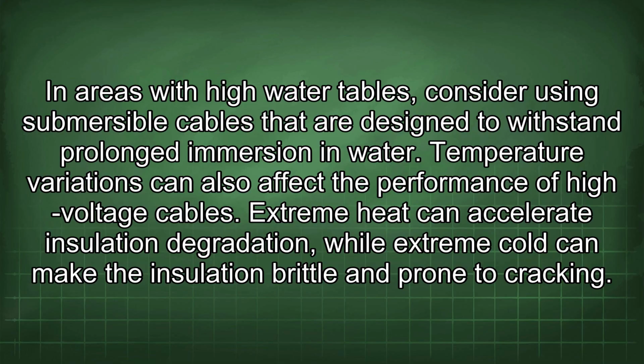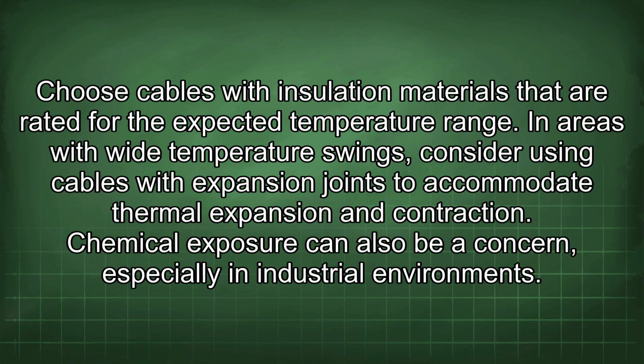Temperature variations can also affect the performance of high-voltage cables. Extreme heat can accelerate insulation degradation, while extreme cold can make the insulation brittle and prone to cracking. Choose cables with insulation materials that are rated for the expected temperature range. In areas with wide temperature swings, consider using cables with expansion joints to accommodate thermal expansion and contraction.